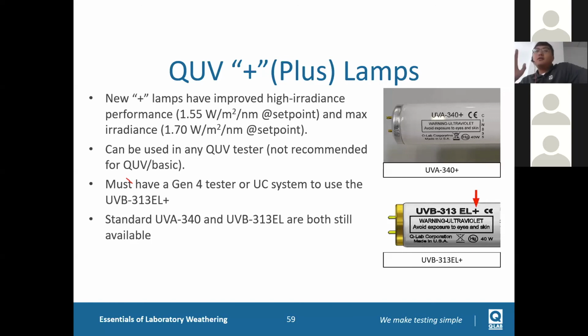But I think 95, maybe 98% of customers only do the typical regular irradiance setting, like based on ASTM G154, it's 0.89, or ISO, 1.77. You do not need the high irradiance setting. So the regular non-plus lamps still exist, and the price is the same, no difference. And for the UVB 313 lamp, we can also do a high irradiance setting. But I think very few people use UVB 313, or even a UVB 313 high irradiance set point. Very few. So if you have the requirement, please contact our distributor Maha for more information.